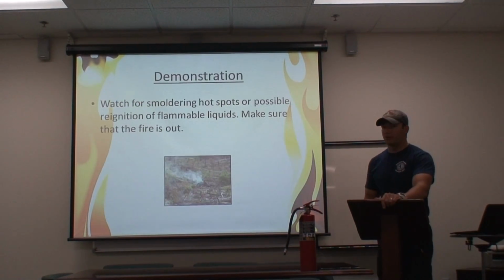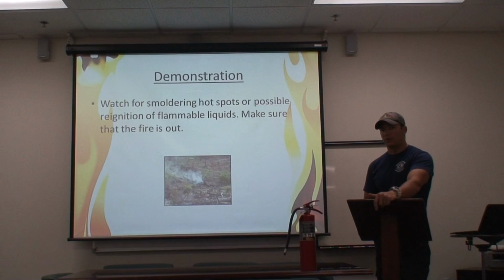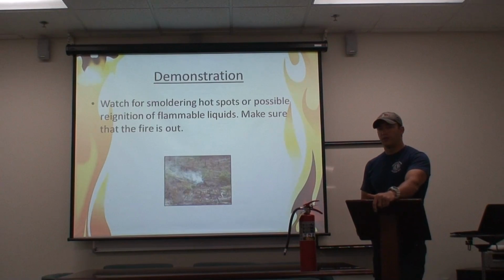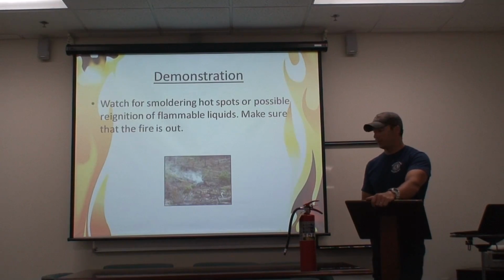All right, you always want to watch for rekindles, watch for the smoldering, reignition of flammable liquids, because like I said, if you're dealing with flammable liquids and it's creating a slick over the top of the flammable liquid to smother it, you want to make sure that film doesn't break through and it restart again, because then you're out of agent, you're in a little bit of trouble. So always want to make sure that the fire's out and do proper overhaul. Make sure that you're good to go, make sure everything's good before you leave and call it under control.